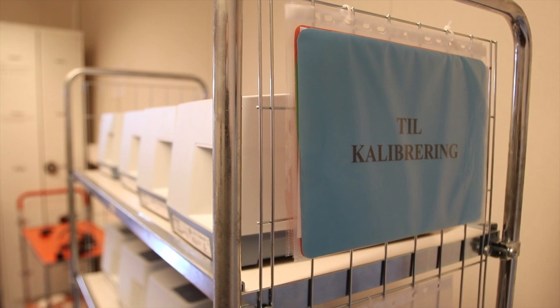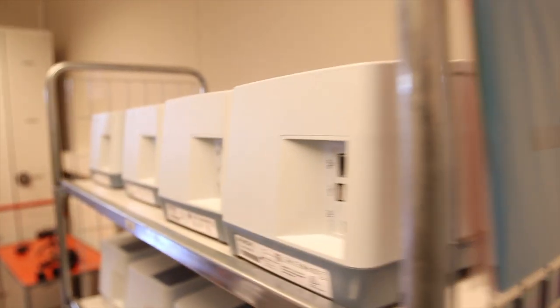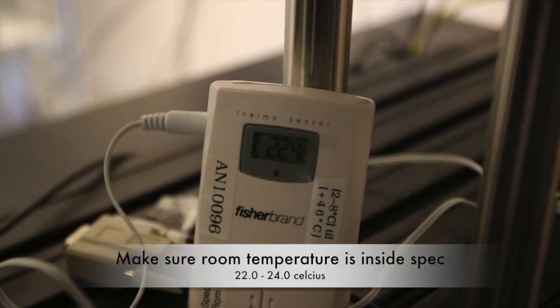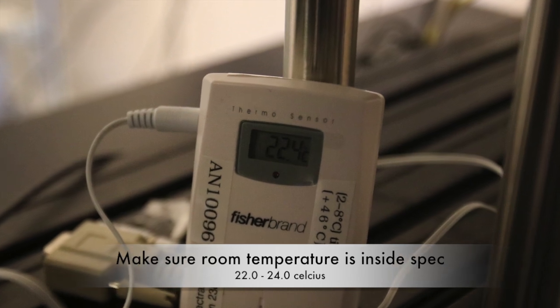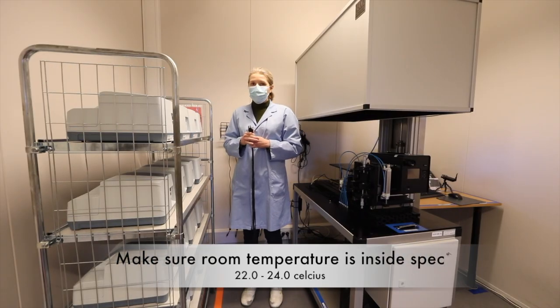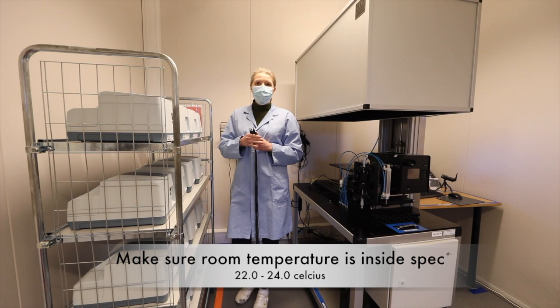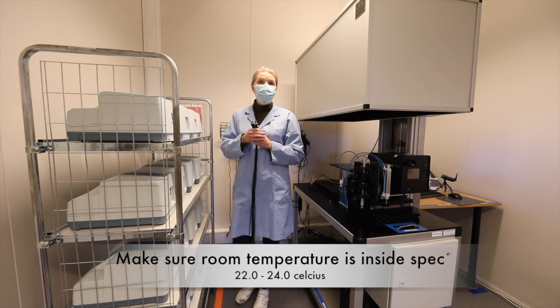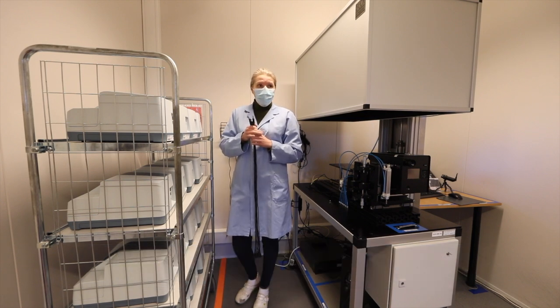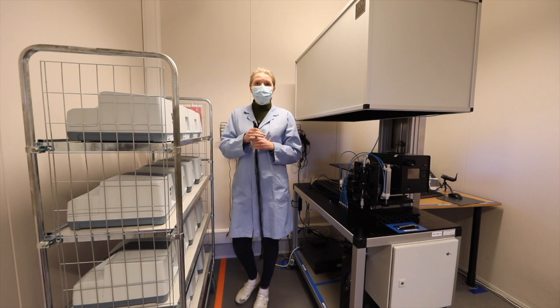All the instruments that are going to be calibrated, including the reference instrument, must be stored in a room temperature controlled for at least 1 hour. The defined room temperature is between 22.0 degrees and 24 degrees Celsius.